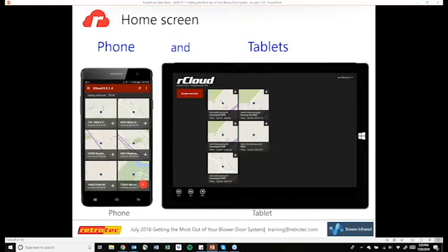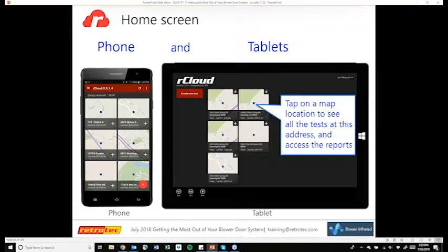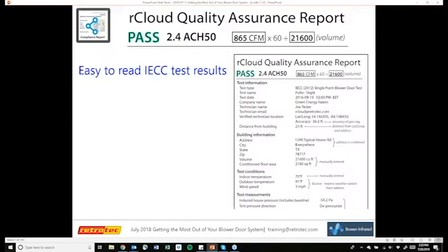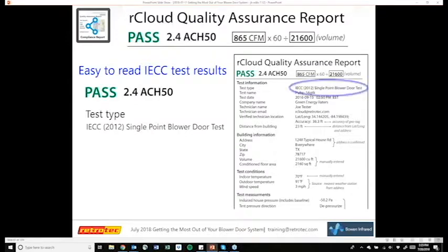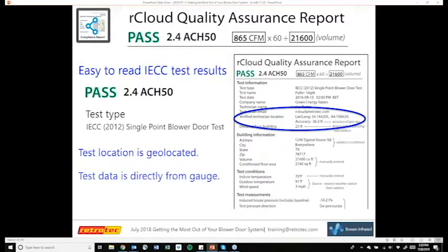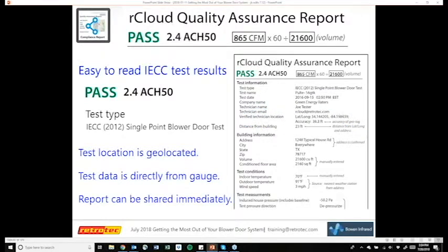So it works on both phones and tablets for both Apple and Android. And it even runs off your Windows PC as well. And the nice thing about this is it gives you a nice report at the end of it. It shows you where you were, the address, characteristics of the house, such as the volume and square footage, what the outdoor temperature was. When you go in and set up the house, you have to manually put in the indoor temperature. And it'll tell you, depending on what your target is, you manually set your target on whatever leakage you're looking for. And at the top, it'll tell you if you passed or failed. So this is really nice to leave with a building official or send to your HERS provider. Your HERS provider loves this.